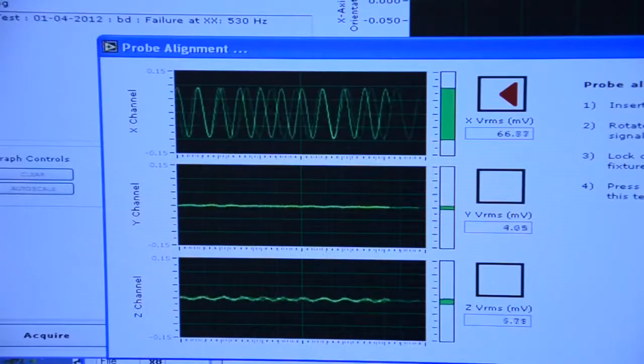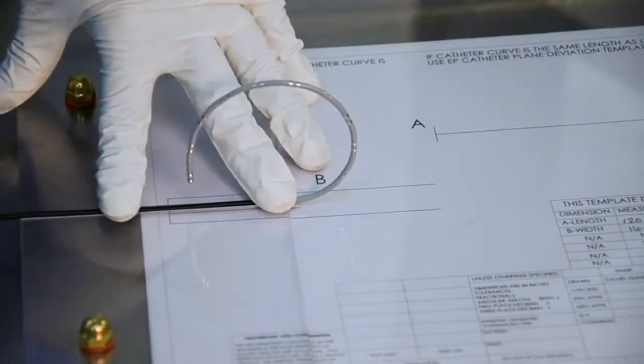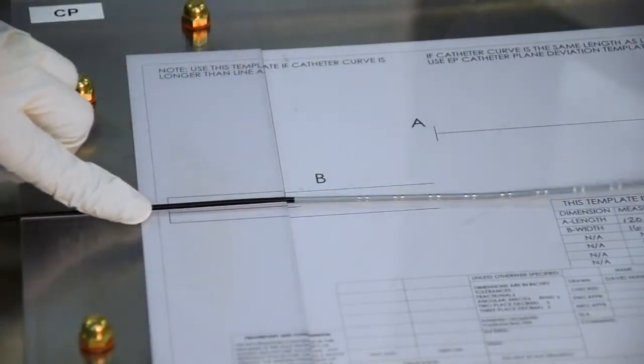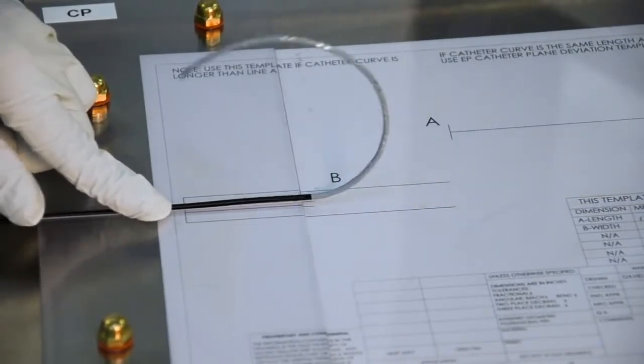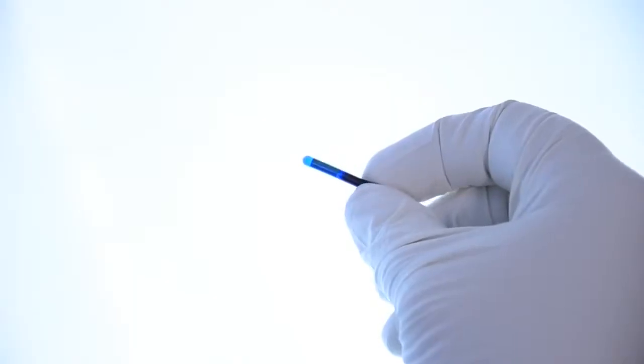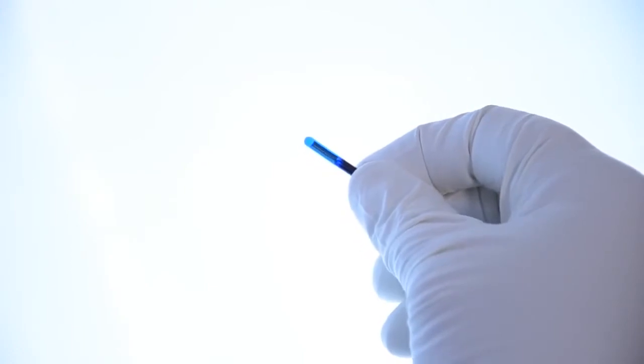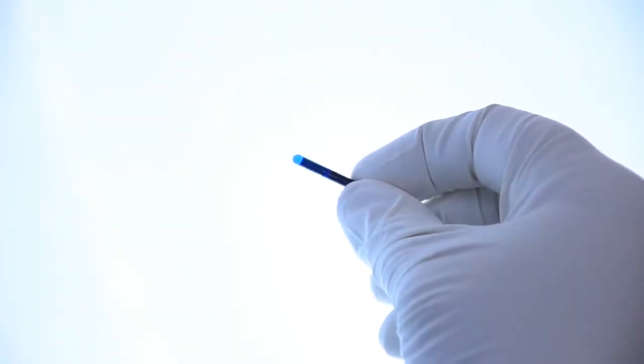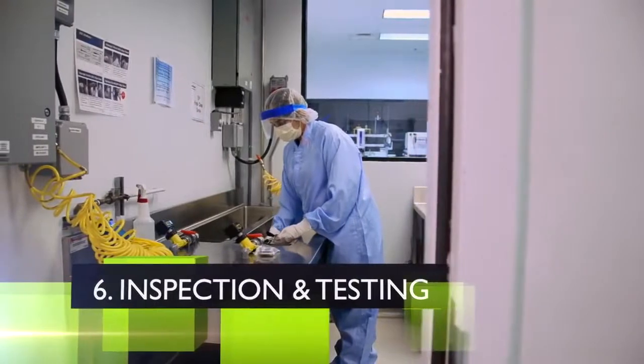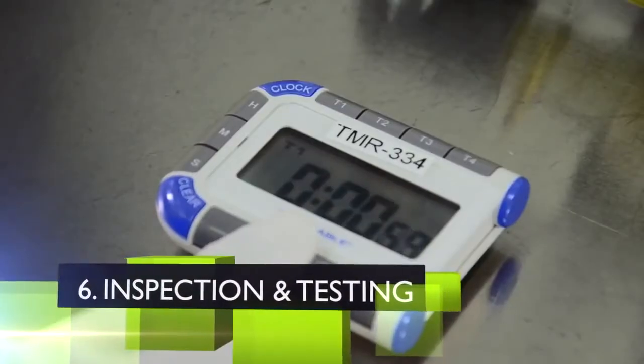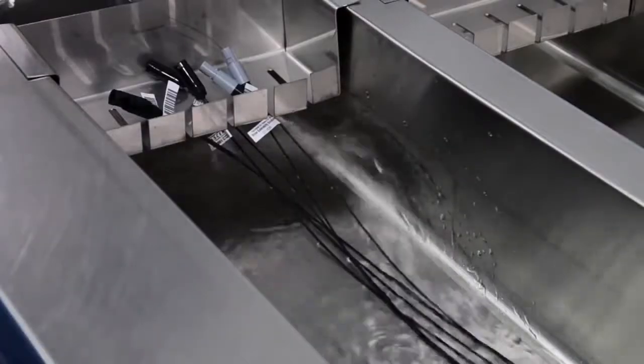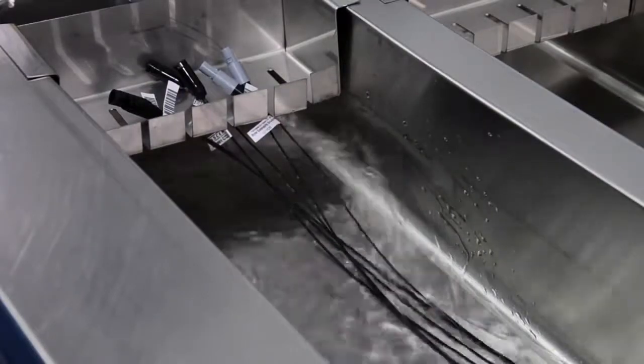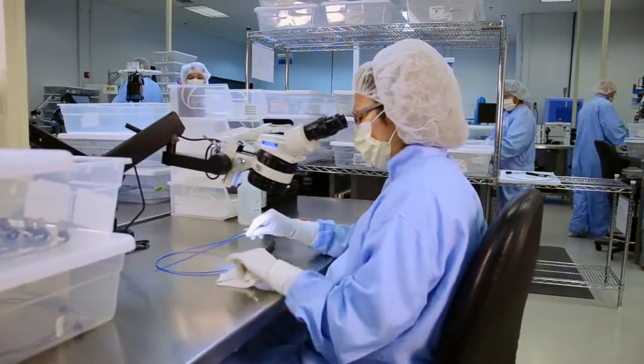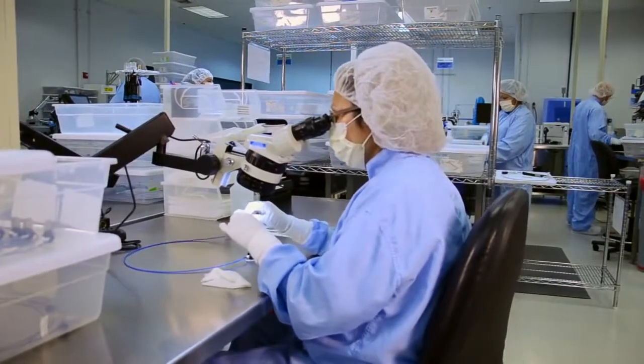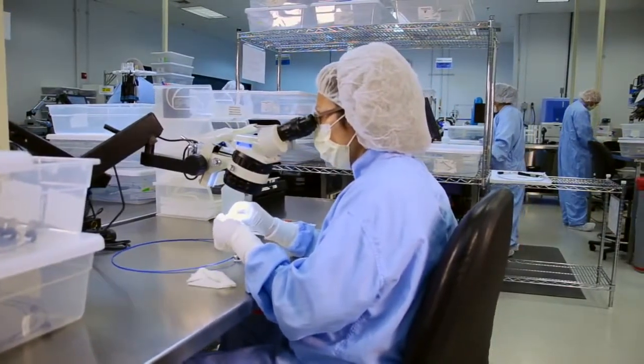Once catheters pass all tests, mechanical integrity is verified to check for deflection and curve performance. Catheters must meet all performance specifications to be considered for reprocessing. Any catheters that do not meet these criteria are immediately rejected and recycled. After functionality is verified, all catheters receive a final rinse with heated, reverse osmosis deionized water. Next, catheters are carefully dried and then inspected under magnification again for any remaining debris or damage.